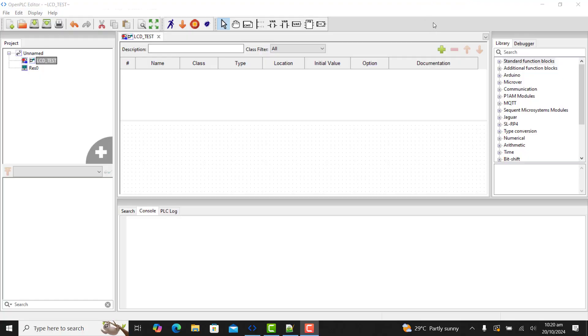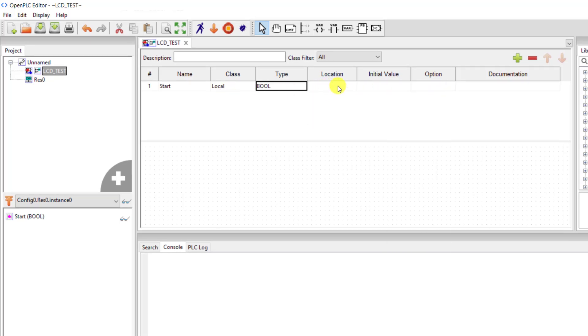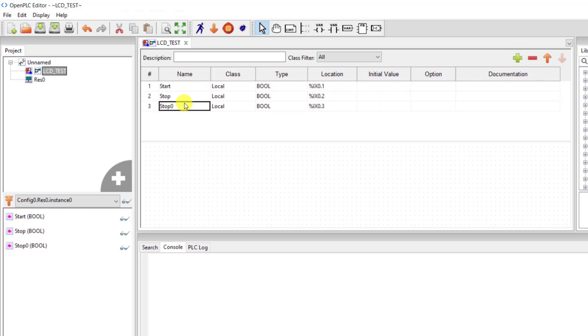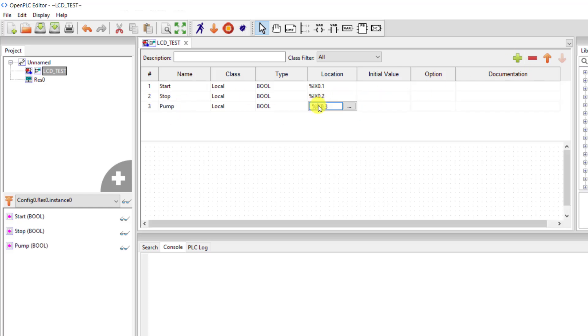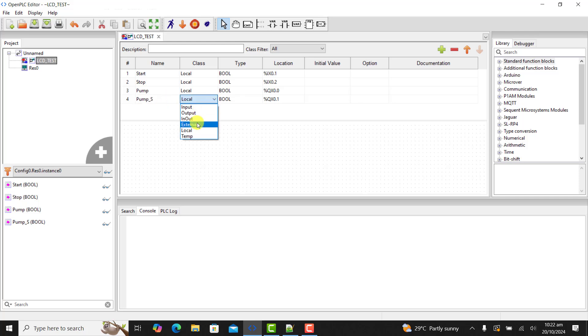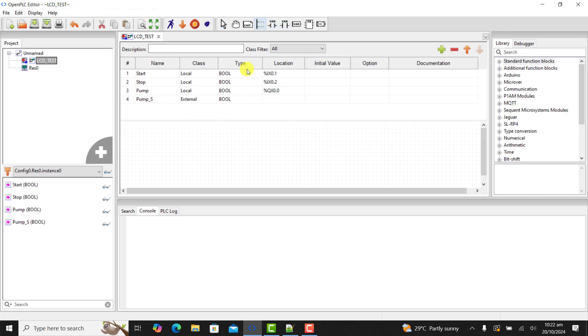We will move on and write our code. We will now do a variable declaration. Our first variable to declare is 'start', assigned to I0.1. Then 'stop', assigned to I0.2. Then we have our 'pump', assigned to Q0.0. And then we have our 'pump state', which will be external, because we need to read it from our sketch.